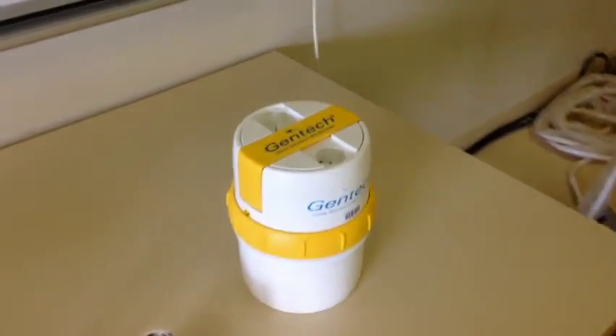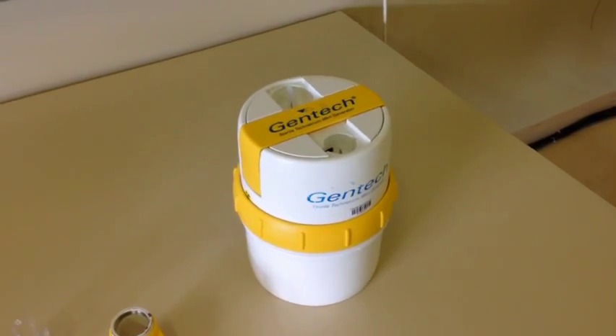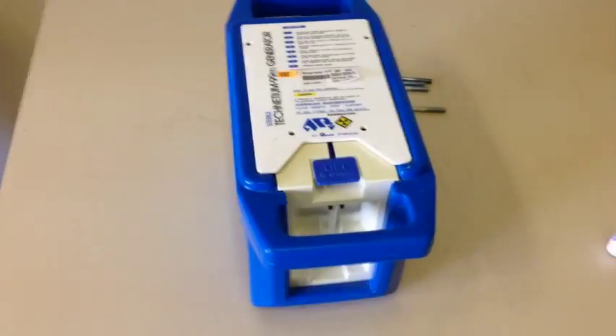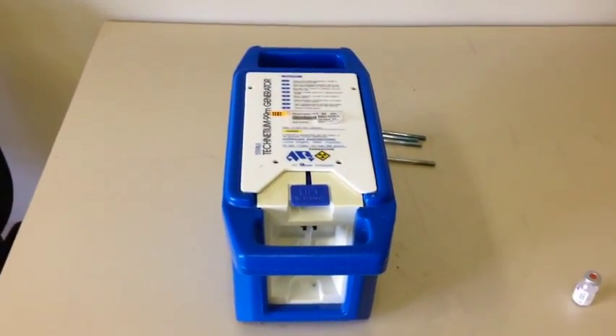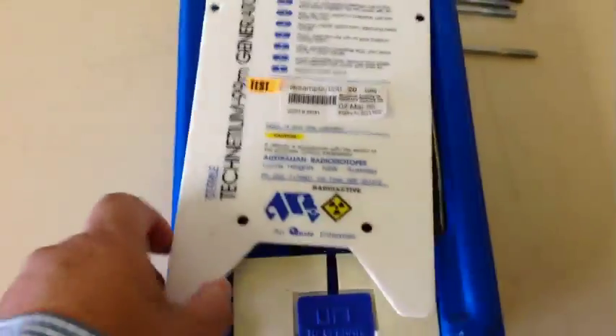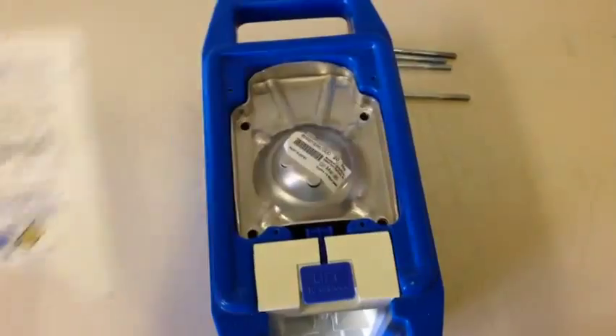This has been superseded by the Gentech generator, which is a dry generator, and I'll explain the difference between the two. These are cold generators with no radioactivity in them. I've popped the top off so you can see the generator, which expired many years ago.